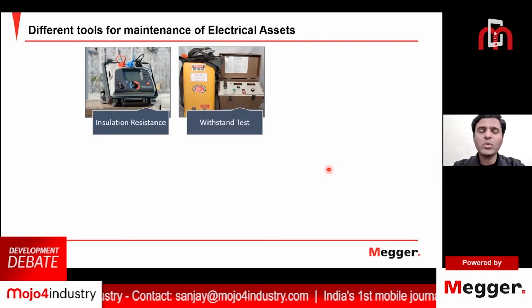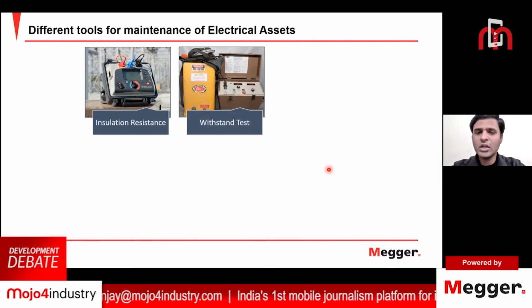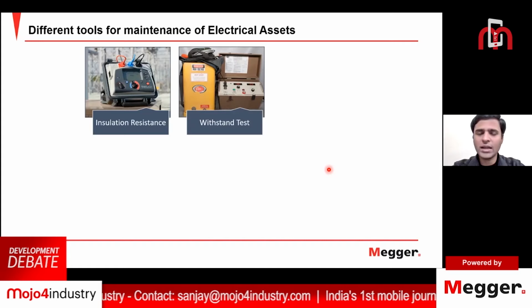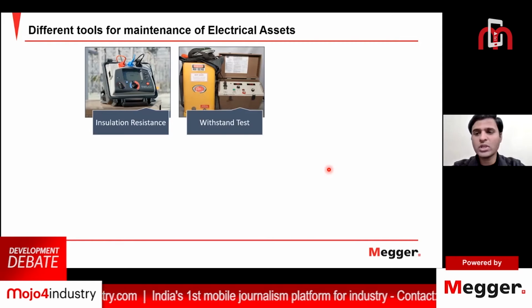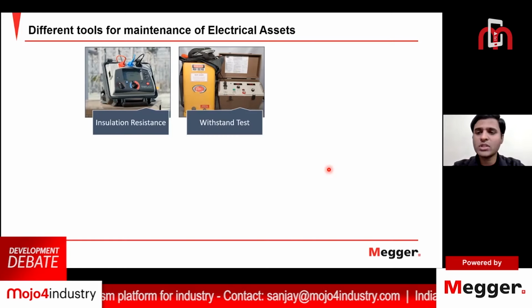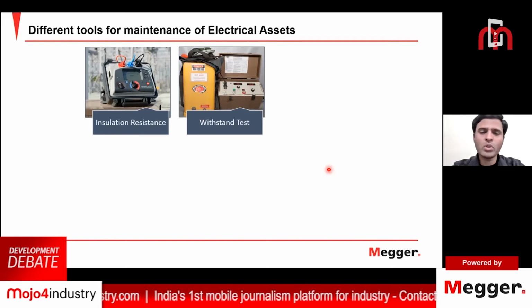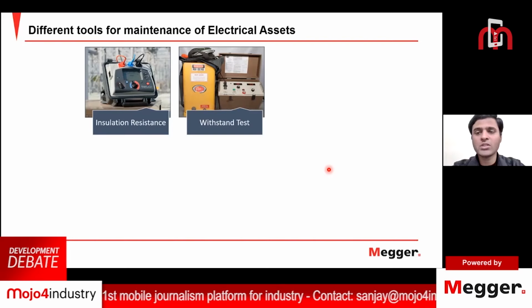After an IR test, many utilities carry out a withstand test on the asset to understand whether it is healthy enough to withstand rated parameters like current or voltage. An AC or DC source is used, and the asset is tested with at least 1 times the rated voltage, or as per standards it may go to 2 times the rated voltage. If your electrical asset is healthy, it should sustain. If it is not healthy, it would not sustain the rated voltage or current. However, this withstand test is also carried out in offline condition. So both these tests help you ensure that there is a fault, but they will not help you predict that there can be a fault in the future.